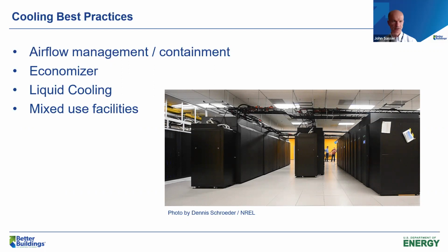The first, and arguably most important for air-cooled servers, is airflow management and containment—physically separating the cold air from the hot air. This allows two things: it significantly reduces fan energy, and it extends economizer hours, the amount of time you don't need mechanical cooling because you can increase the discharge temperature of the air handlers. We'll cover that more in a later slide.